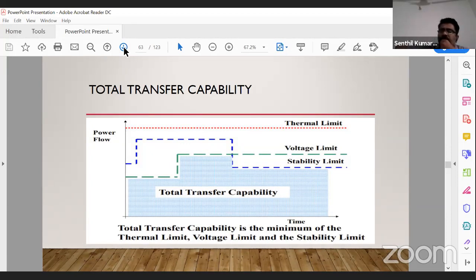When the thermal limit is reached, in case of any tripping, the feeder flow reaches a higher side - that is the thermal limit. So for twin-moose conductors, total transmission capacity is 1000 megawatts. The thermal limit is 874 megawatts, voltage limit is 720, and stability limit is 515 megawatts. Normally, as per transmission criteria, we allow only 515 megawatts.